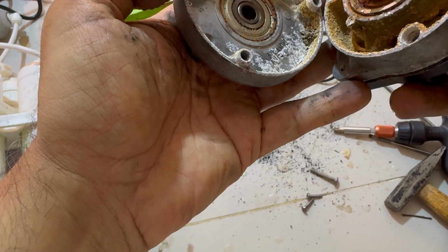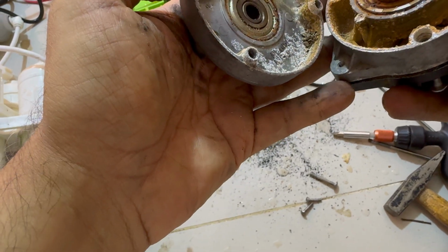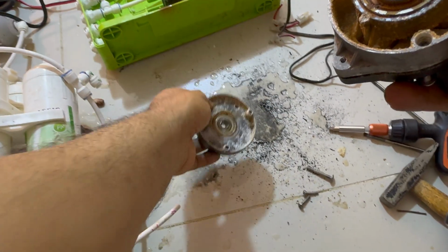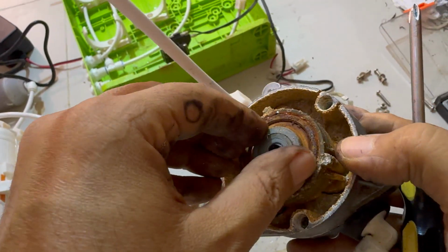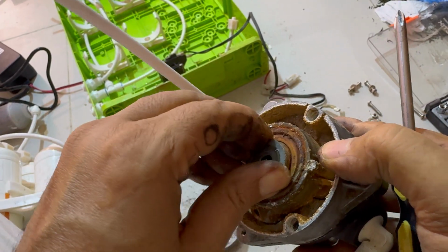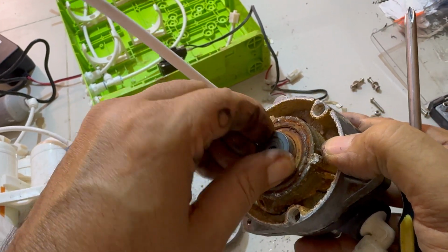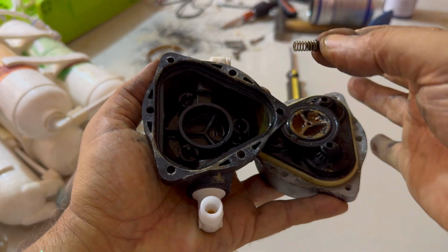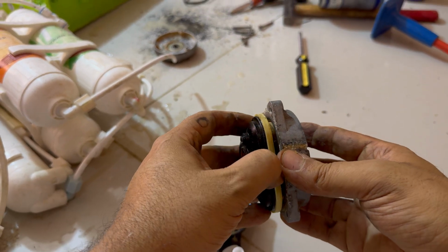So it wasn't the dynamo itself, it wasn't the motor itself, but the pump that is attached to the motor, mainly this one here. Oof, it's very hard. So this is the problem. The pump is actually plugged in the first part, and that's why every time I install an adapter, it burns out and destroys it.